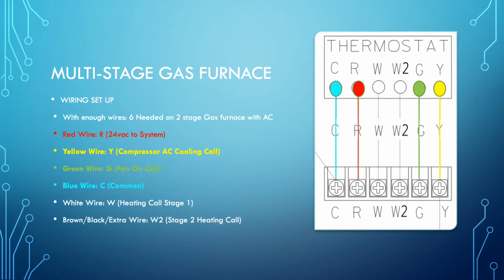Now, our blue wire, if there's a blue wire available, it will be used for the common leg. And once again, I understand that Rheem is brown and other brands might have a different color inside the actual equipment. However, the wiring in between the equipment and at the thermostat, common is your blue wire. On a gas furnace, the white wire is used for a heating call, so you'll place it on W. And this is a stage 1 heating call.